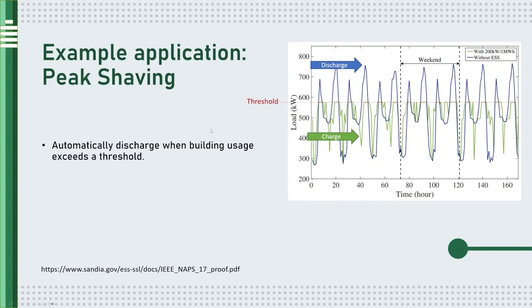Worse, if you set the threshold too low, you might run out of energy first. You might run out of gas in the tank, of energy in your batteries, at which point you would stop discharging, and your utility meter would read something very high, and now you've set your demand charge for the whole month at this high level. You're going to get hit with a high bill.